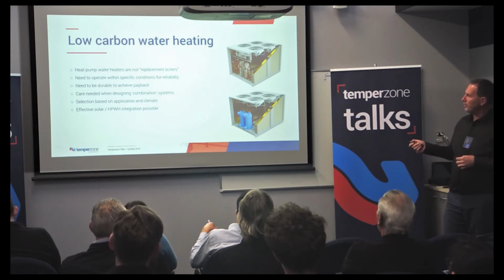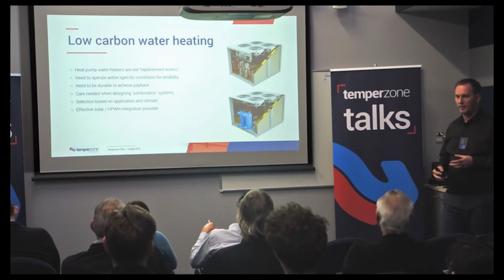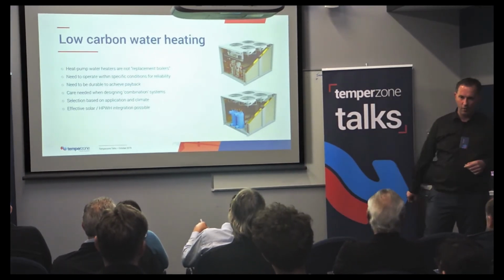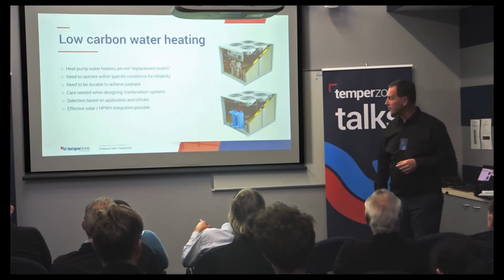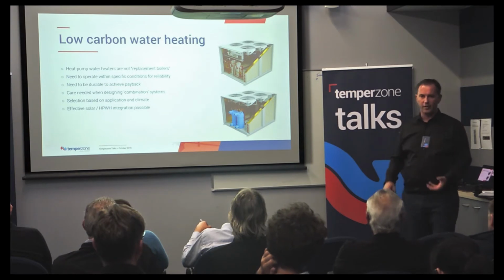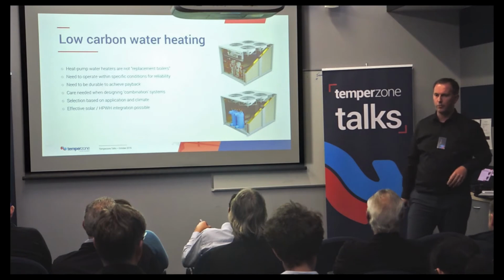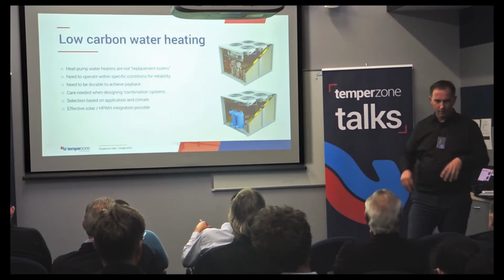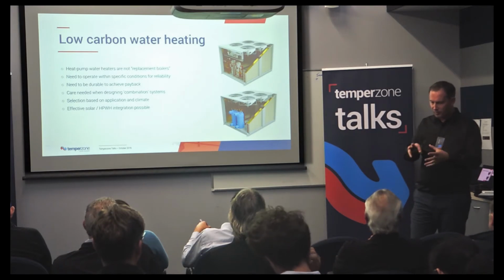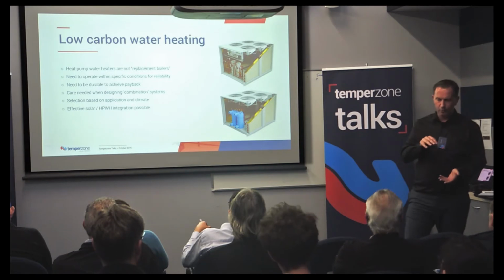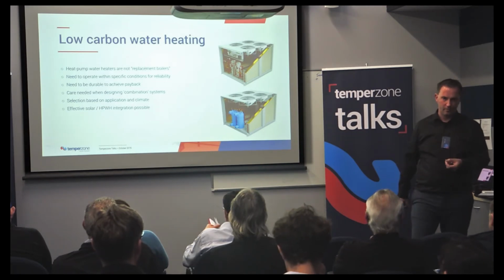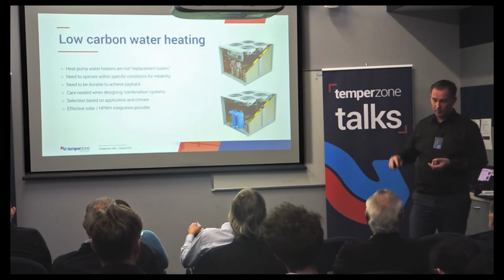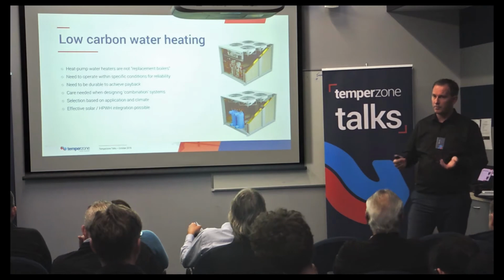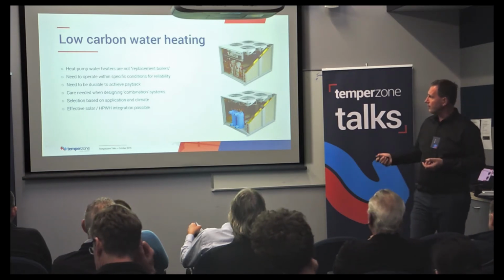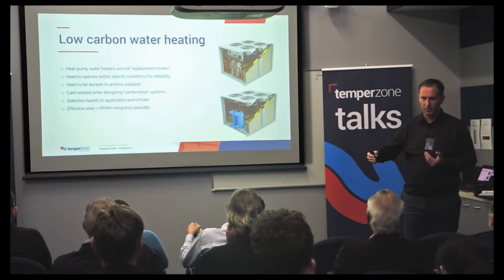So, heat pump water heaters are not replacement boilers. You can't say, I need a gas boiler, so I'm just going to drop in a hot water heat pump. Much of the industry does this, and what you see after 4 or 5 years is that the top of the compressor will usually be quite discoloured, quite burnt, quite dull. The paint's quite dull, and it's just because the compressor's been operating outside of its envelope. They usually sit mostly between 50 and 60 degrees C water temperature, and they're not terribly durable if you do that.